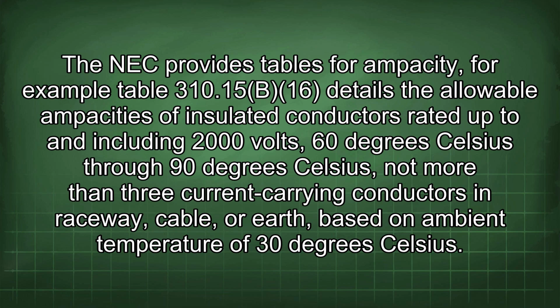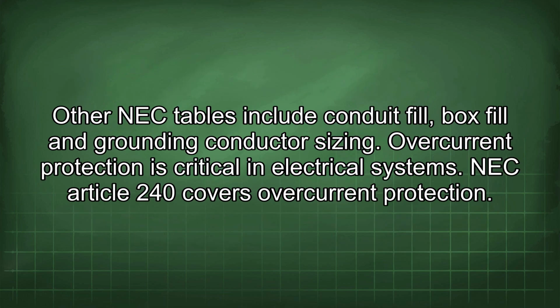For example, Table 310.15(B)(16) details the allowable ampacities of insulated conductors rated up to and including 2000 volts, 60 degrees Celsius through 90 degrees Celsius, not more than 3 current-carrying conductors in raceway, cable, or earth, based on ambient temperature of 30 degrees Celsius. Other NEC tables include conduit fill, box fill, and grounding conductor sizing.